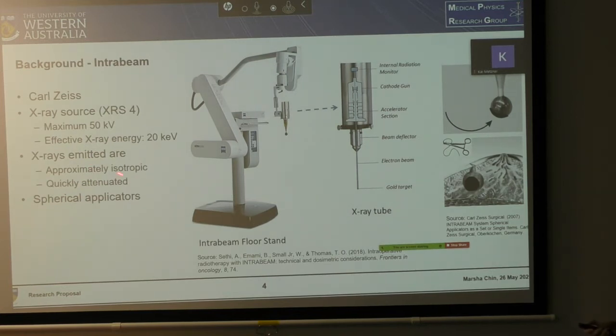The X-rays emitted are approximately isotropic, so uniform in all directions, and the X-rays are also very quickly attenuated in water and in tissue. We've also got spherical applicators, which are these things here that sit over the X-ray probe. And in the X-ray probe, you've got an electron beam that is accelerated down the probe and it hits a gold target here, where bremsstrahlung X-rays are produced.